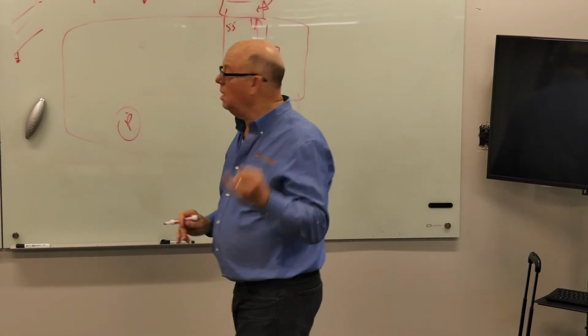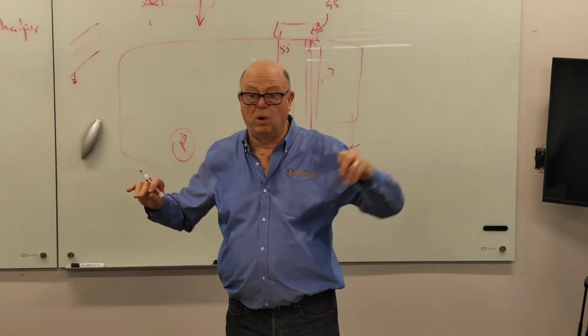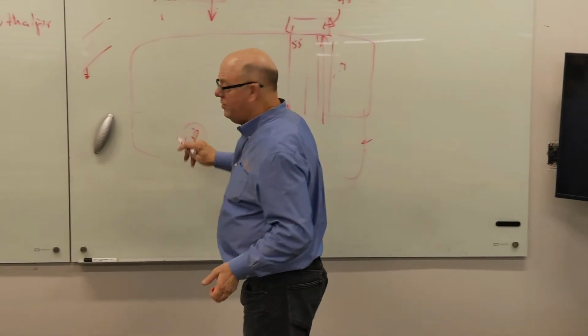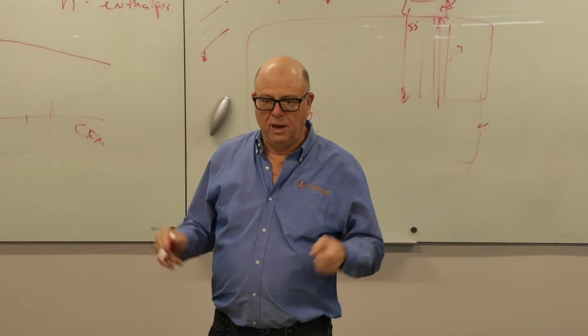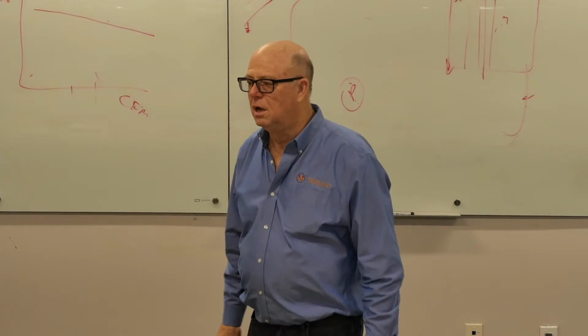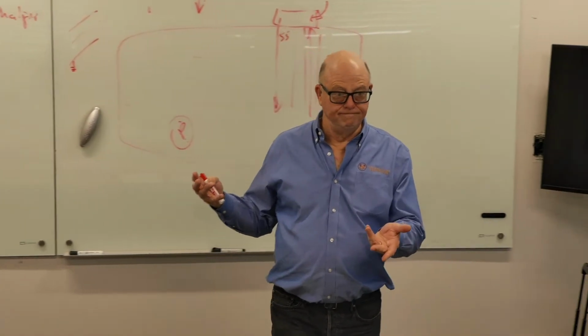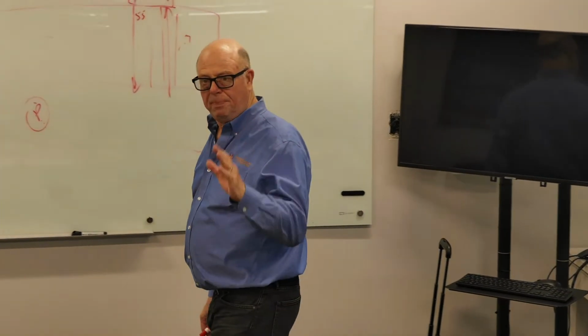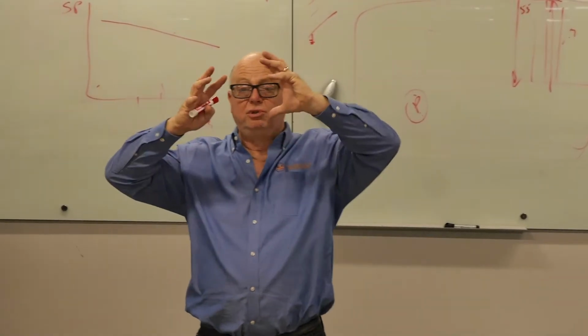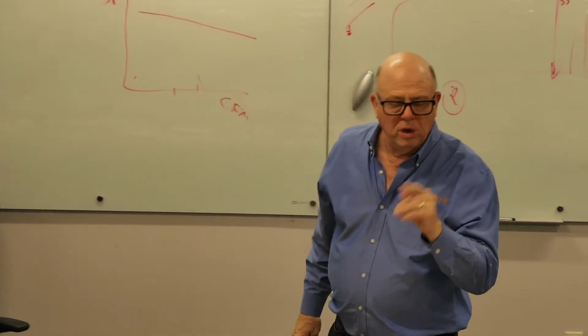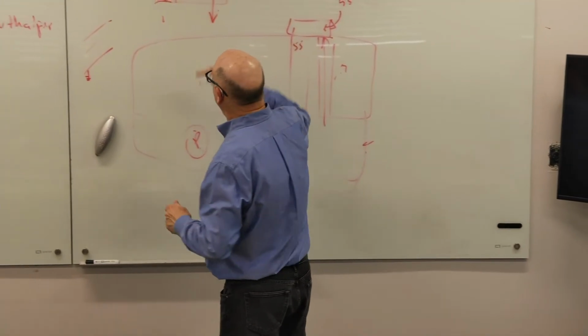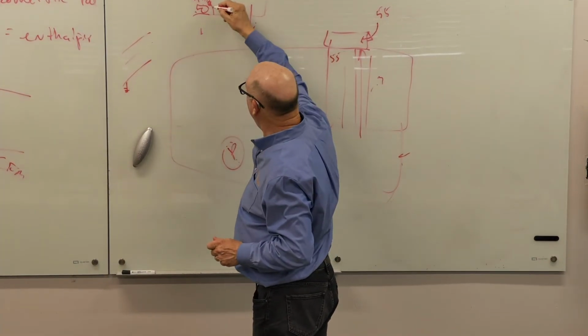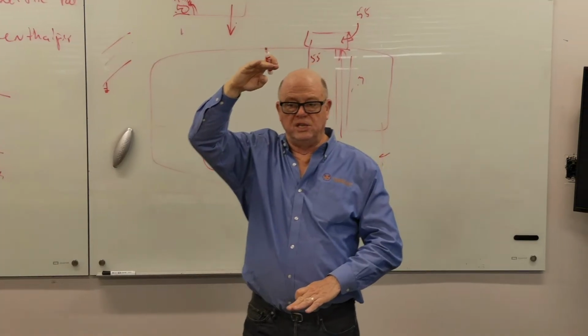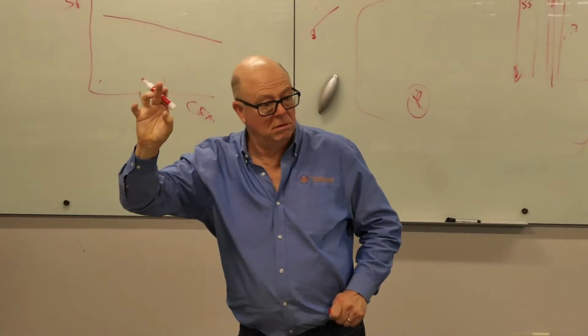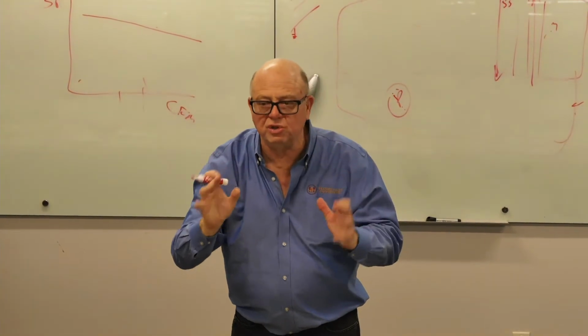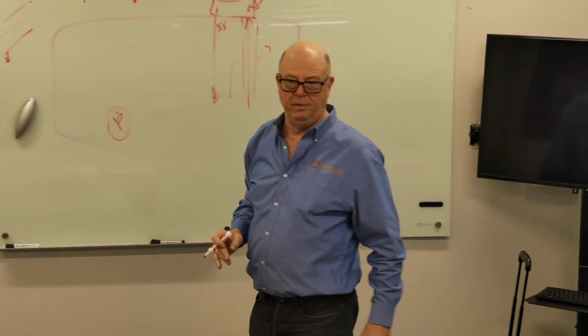So it's quiet, and it would work off of the pressure, and you'd set it for whatever pressure you wanted to maintain. Pressure sensors usually have what's called a reference. What's a reference? Baseline. Baseline, yeah. Typically, if you're controlling off pressure, there are two situations. One, you might be just reading the pressure in the pipe or in the duct. The other, you may be comparing it. And we would be comparing it. So this pressure sensor would be reading the pressure in here, and it would also have a little pickup tube right there on the roof. So you were comparing the ambient pressure with the pressure inside the building. That differential is what you wanted to keep under control so it didn't blow the doors open and whistle.